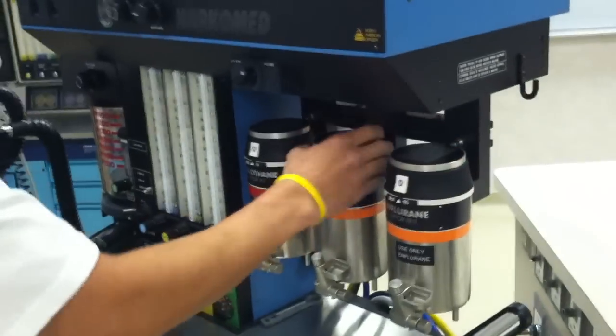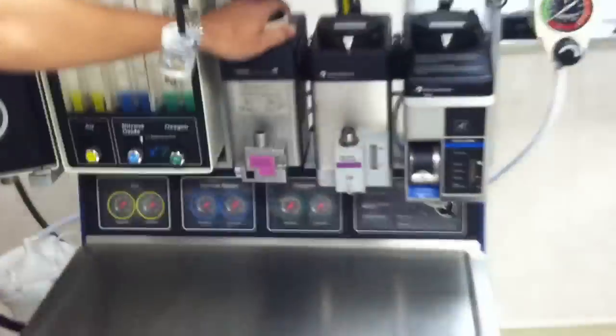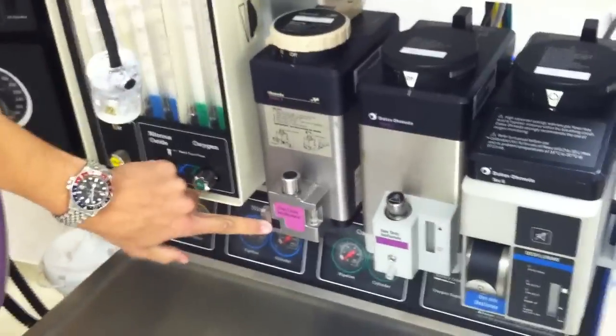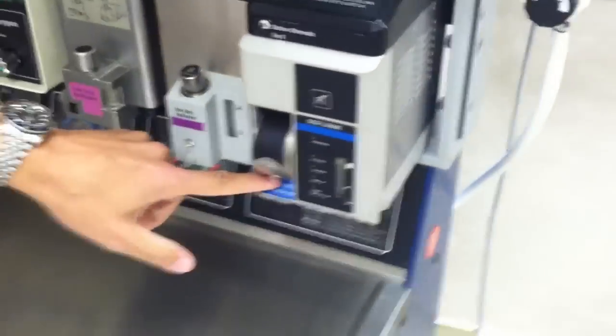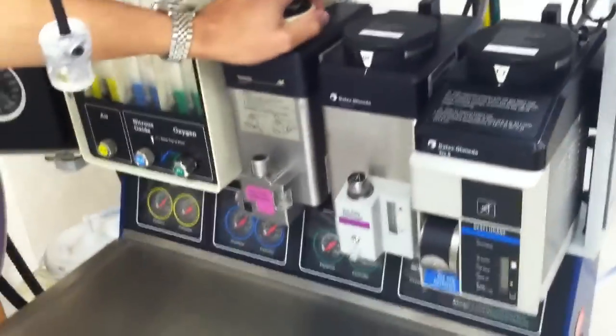Check your interlock systems. More than likely on these machines, you're going to have these vaporizers here. This has their key fill. This is your funnel fill and your desflurane. So same thing, you want to make sure that the interlock system is working. So now that we've checked that, we can go ahead and turn on our machine.